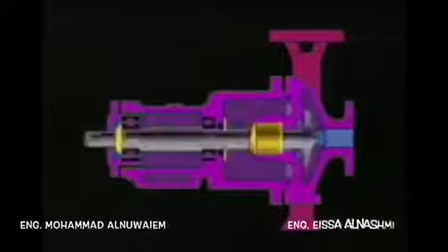Contrary to popular belief, mechanical seal design and operation is relatively simple. Basically, it consists of two flat faces: one stationary, mounted in the gland, and one rotating with the shaft in a circular motion.